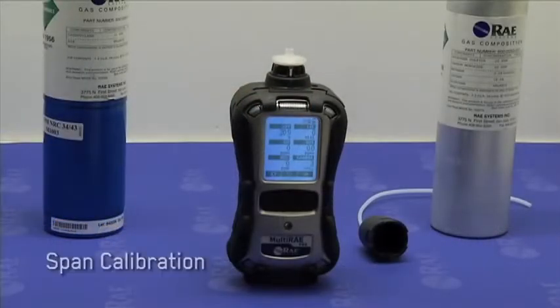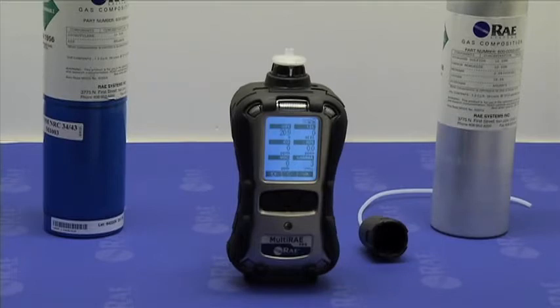Let's get started. RAE Systems recommends that your MultiRAE be fully span calibrated on a periodic basis in accordance with national and regional regulations, but no less frequently than every 180 days. The span calibration can be performed automatically using the RAE Systems AutoRAE 2 test and calibration station. This video is going to cover the manual span calibration process.